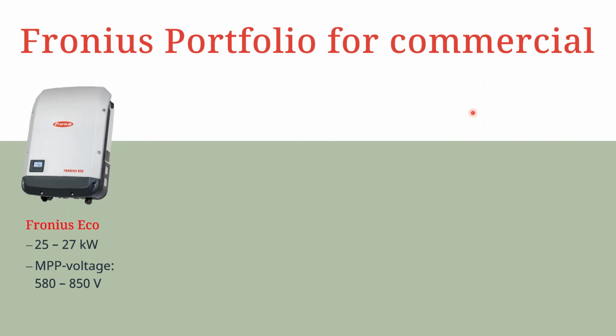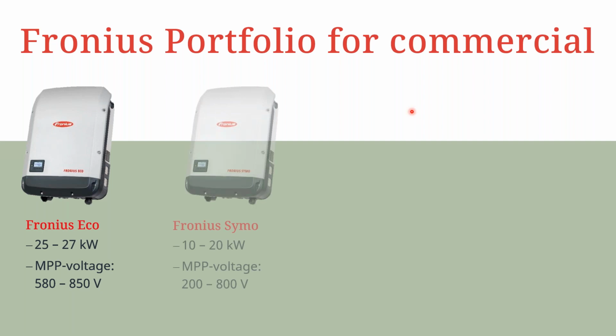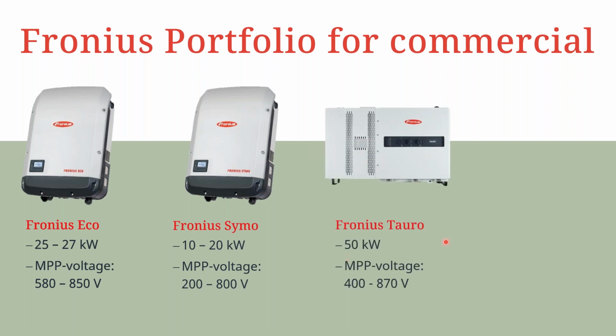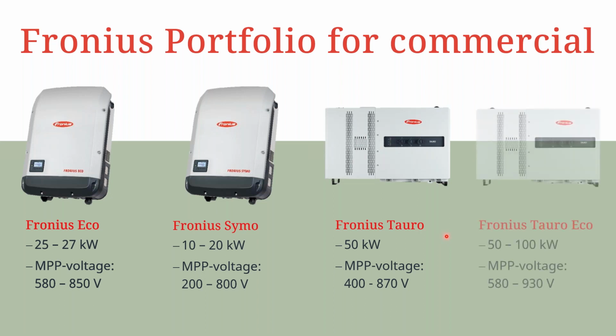So looking at the Fronius portfolio for commercial systems, we have 3 specific inverters that can be used for this purpose, starting with the Fronius Eco inverter, which is available in the power classes 25 and 27 kilowatts with an MPPT voltage of about 580 to 850 volts. Then you have the Fronius Symo available in the power classes 10 up to 20 kilowatts. The MPP voltage is about 200 to 800 volts DC. We do have also 2 Tauro variants. The first one is the Fronius Tauro Standard, which is 50 kilowatts. MPP voltage is 400 to 870 volts. Then you have the Fronius Tauro Eco, which is available in 2 power classes. One is 50 kilowatts and the other one is 100 kilowatts. The MPP voltage is 580 to 930 volts.